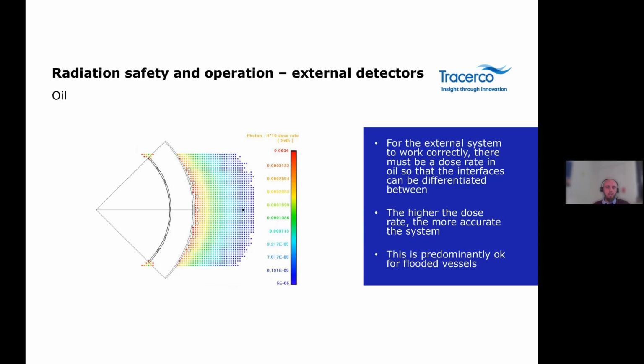So, a little case study on the dose rates that are seen using this system. This case study was completed to analyse the whole body dose rate implications of an external system. The radioactive source inside the standard conventional instrument is made up of 7 source capsules, each containing 30 millicuries of cesium-137. Typically, the higher the dose rate of the system, the more accurate the results are going to be, as there's a large change in count rate that is observed. But this gives a much higher dose rate on the external vessel wall, as shown in the graphic.